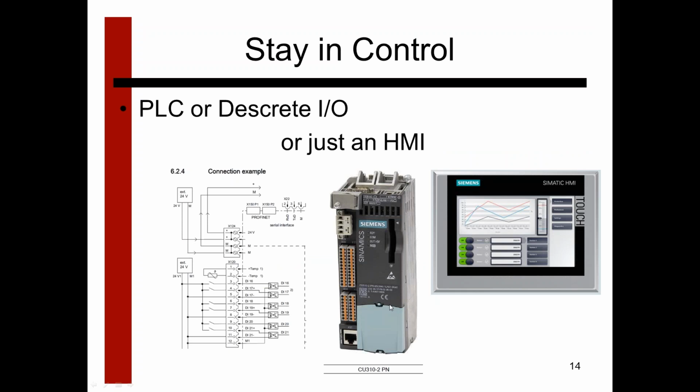So now that we've got a mechanical system selected, we've got a motor selected, we've got a drive selected. Now I'm going to ask questions about how do you want to control this application? Single axis applications, believe it or not, can still be controlled by simple push buttons. Today's drives have the ability to be pre-programmed with index moves, and I had a customer just last month. They simply wanted a drive to do the same thing every day of the week, move out 30 inches, pause, operator push the button, move back 30 inches.